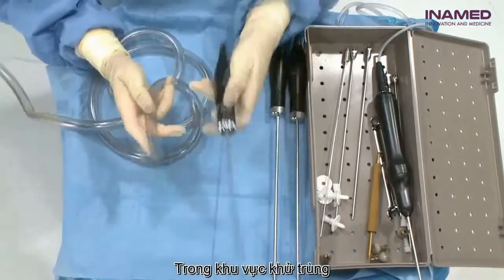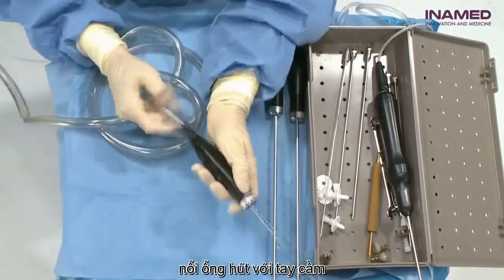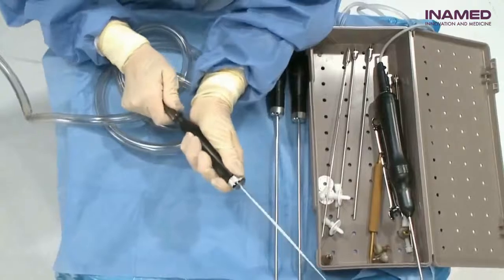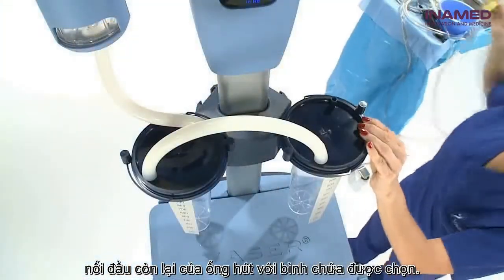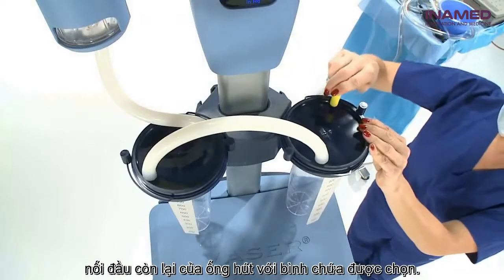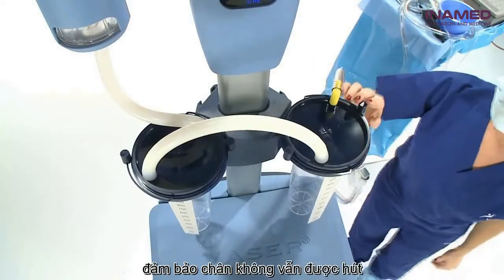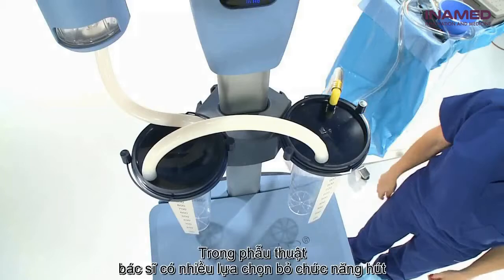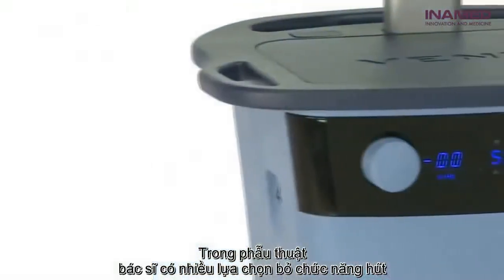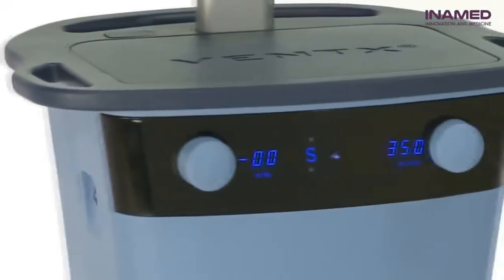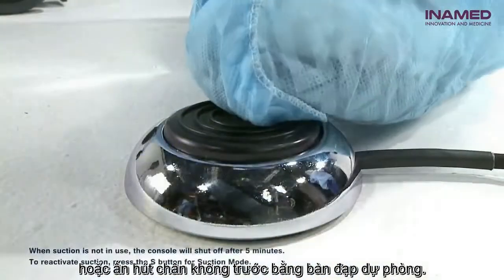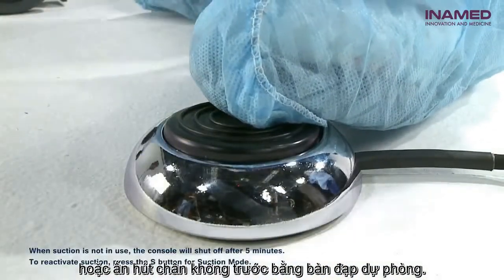In the sterile field, connect the suction tubing to the suction cannula handle. Attach the other end of the suction tubing to the selected suction canister. Ensure vacuum is still engaged to suction. During surgery, the physician has the option to leave the suction on during the aspiration phase or exercise the ability to precisely control the vacuum with the electronic foot switch.